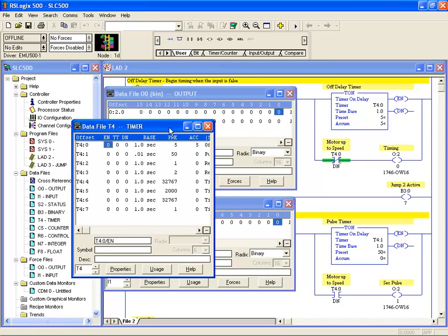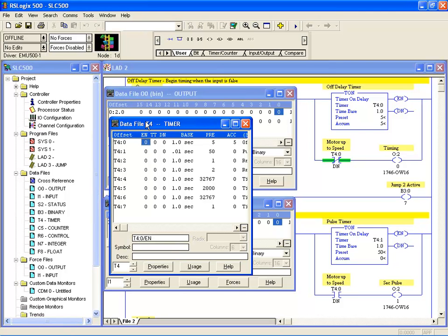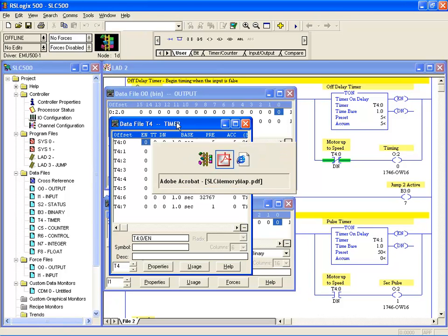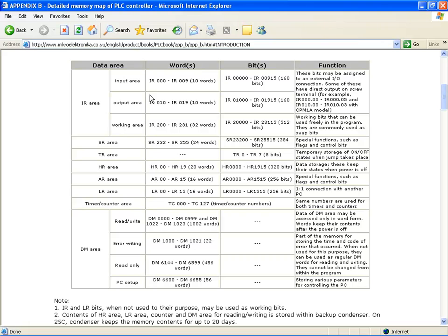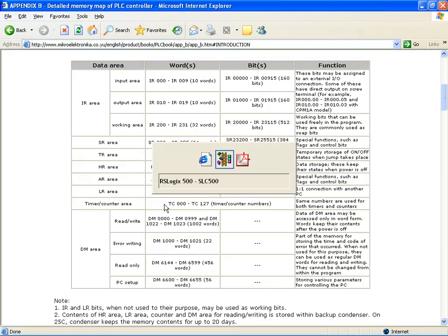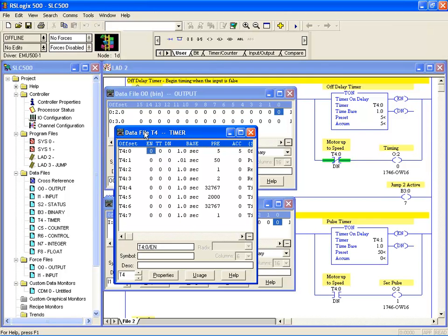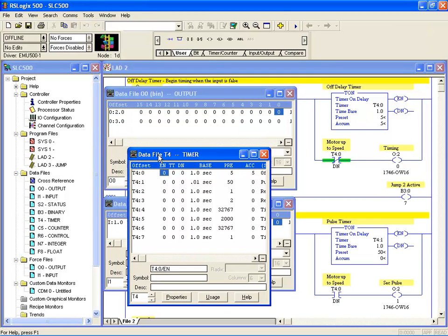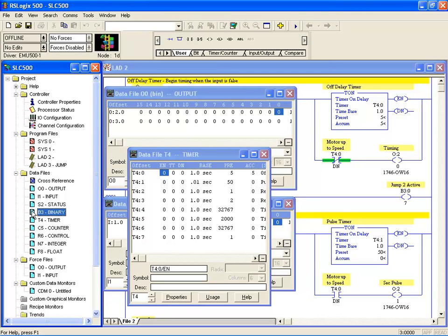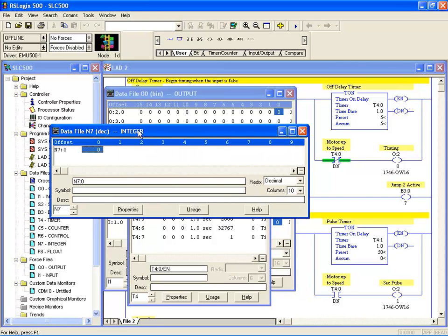One thing about the SLC is that it defines memory only as you use it. So it's memory efficient compared with the older memory map type of PLC where the memory is defined and used at the beginning of your program. You are limited to the number of timers and counters you can have, whereas in the SLC it's a memory defined allocation. The more timers and counters you have, the less other things you can have such as binaries or integer words.